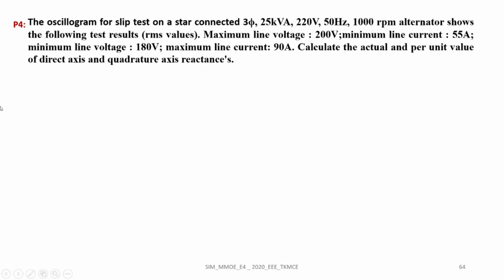Coming to the fourth problem, this problem is related to slip test. The oscillogram for slip test for a star connected 3-phase 25 kVA 220 volt 50 Hz 1000 rpm alternator shows the following test results, that is RMS values. Maximum value of voltage is 200 volt, minimum line current is 55 ampere, minimum line voltage is 180 volt, maximum line current is 90 ampere. Here we need to calculate the actual and per unit value of direct axis and quadrature axis reactances.